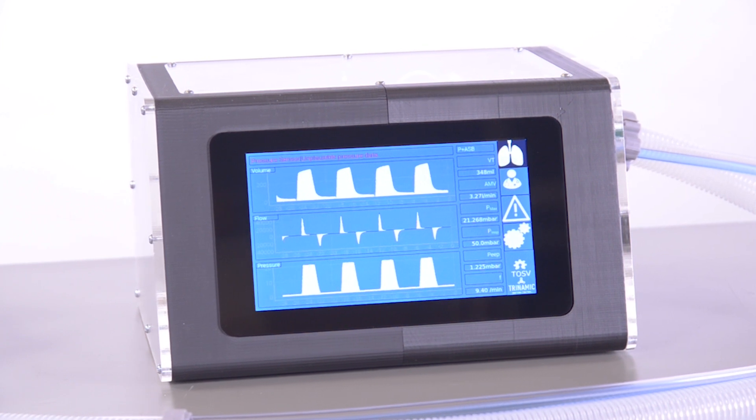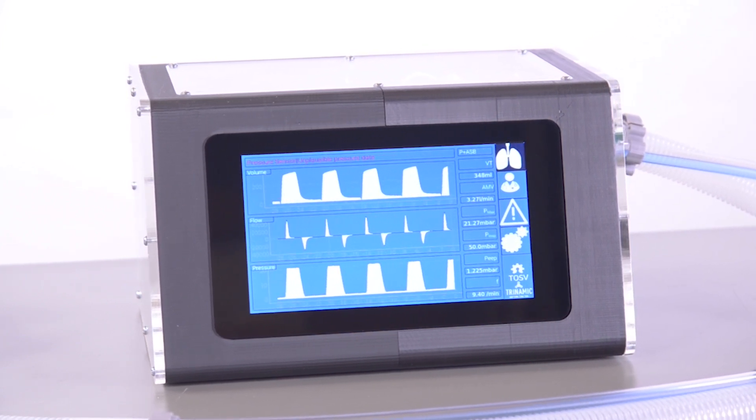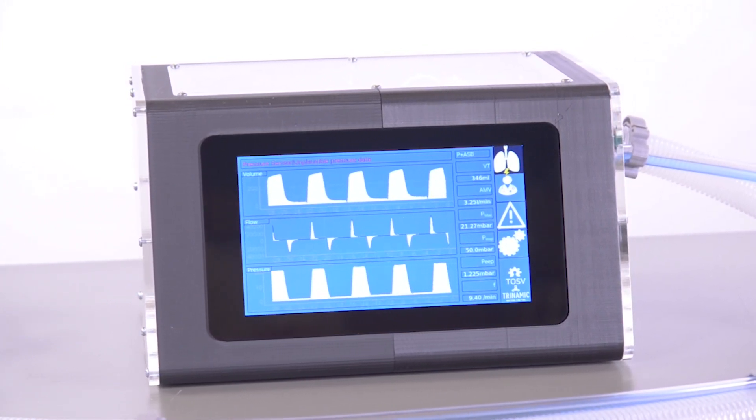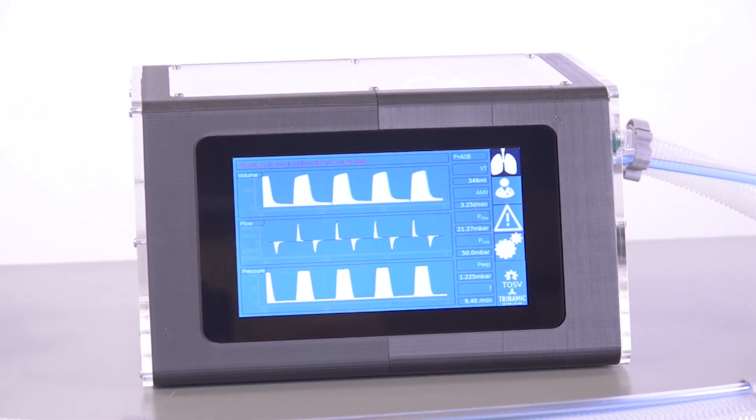TOSV measures the proximal airflow and provides rudimentary implementations of volume-oriented and pressure-oriented ventilation modes. We published the software as well as the electronics design and the mechanical assembly as open source under the MIT license. We are happy to see anyone picking this development up, finalizing it, and saving lives.